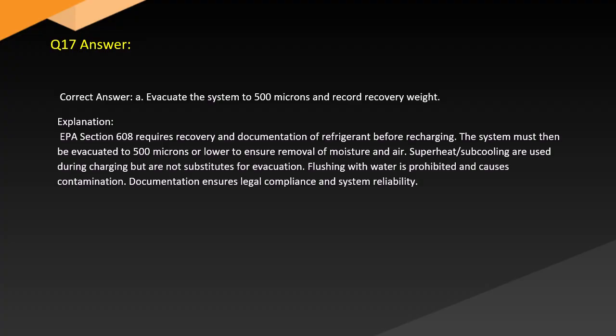Answer. Correct answer: A. Evacuate the system to 500 microns and record recovery weight. Explanation. EPA Section 608 requires recovery and documentation of refrigerant before recharging. The system must then be evacuated to 500 microns or lower to ensure removal of moisture and air. Superheat or subcooling are used during charging but are not substitutes for evacuation. Flushing with water is prohibited and causes contamination. Documentation ensures legal compliance and system reliability.